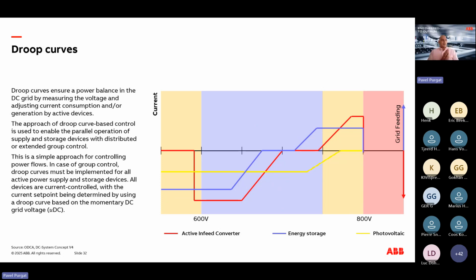And then for the energy storage, photovoltaic and active front end, you decide how much current each is providing in different sections. So that, for example, when we have very high voltage because there is a lot of sun, then for sure we will be charging the energy storage. At the same time, when the voltage becomes too high, we will also curtail the power provided by photovoltaics, and we will feed back to the grid if necessary to ensure that the DC system voltage does not go too high. If it goes too high, then we need to disconnect.